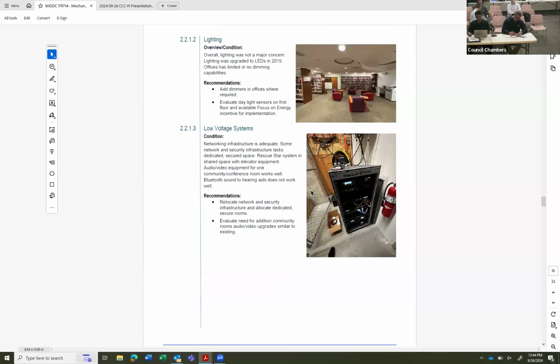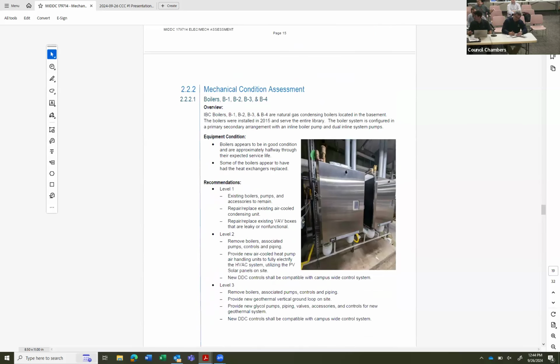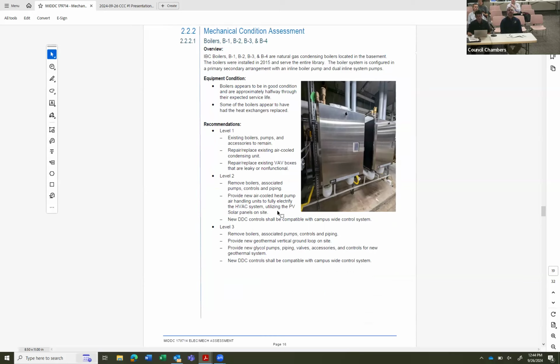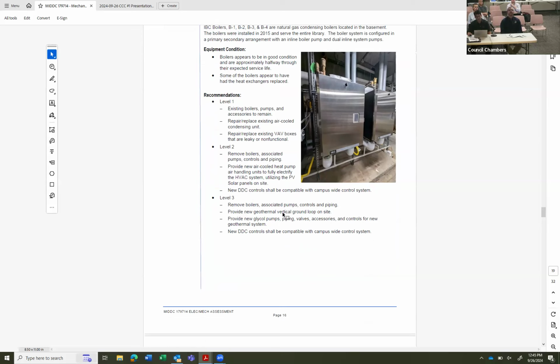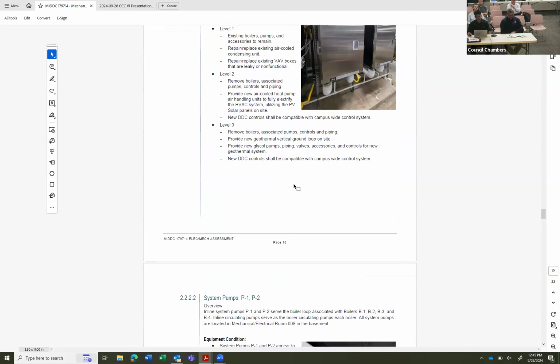So moving on to the library. Sure. All right, I'll speed this along in the effort to not go over time, and remain pretty high level for the rest of these. In the library, there are fairly new high efficiency condensing boilers. The level 1 recommendation would be to keep those boilers and make any repairs to the existing condensing units that are having issues, and replace any VAV boxes that are non-functional or leaking. Level 2 would be removing the boilers and replacing with the VRF system that I had described. And level 3 again would be removing all the boilers and replacing with the geothermal system.